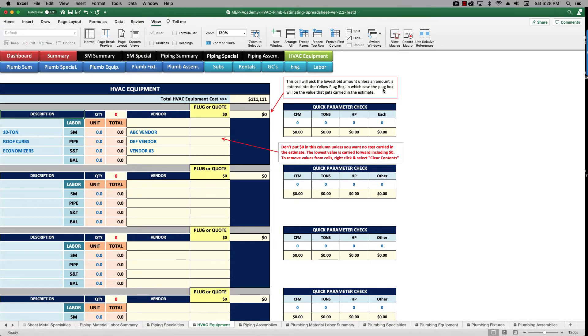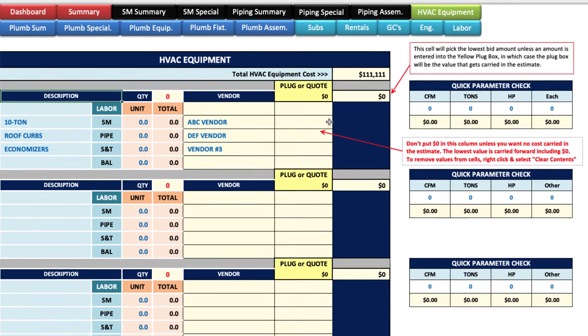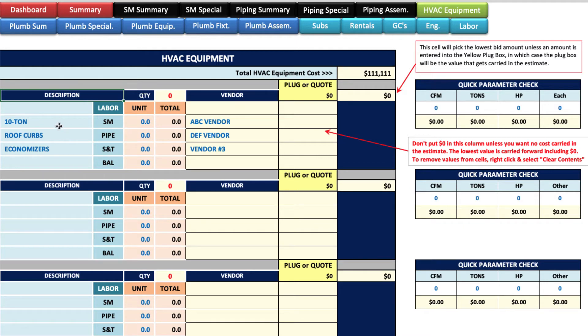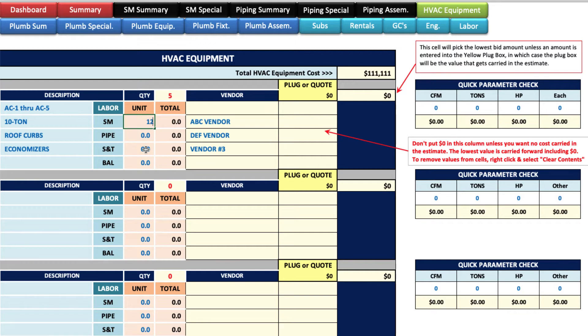This is your HVAC equipment sheet. What you'll do is take off all the equipment shown on the equipment schedules of your drawings and list them here. You can put the tag numbers AC1 through AC5. Let's say they're 10-ton units with roof curbs and economizers — five of them. Then you put how long it's going to take to install each, say 12 hours, with piping, start and test two hours, balance one hour. Whatever your typical hours are, put them here and it'll multiply out based on your quantity.